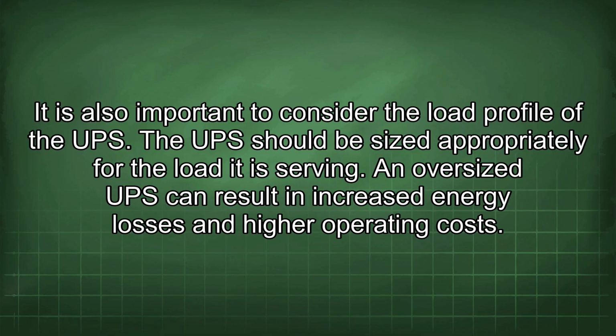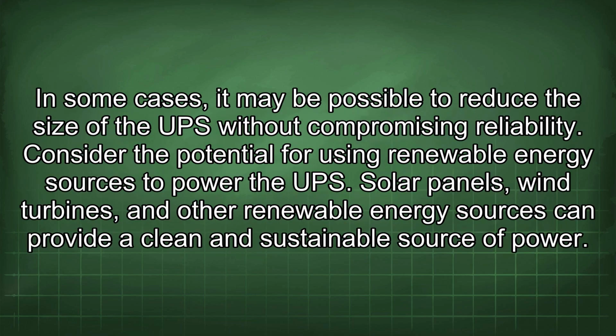The UPS should be sized appropriately for the load it is serving. An oversized UPS can result in increased energy losses and higher operating costs. In some cases, it may be possible to reduce the size of the UPS without compromising reliability. Consider the potential for using renewable energy sources to power the UPS.